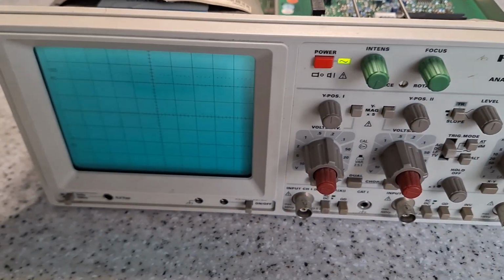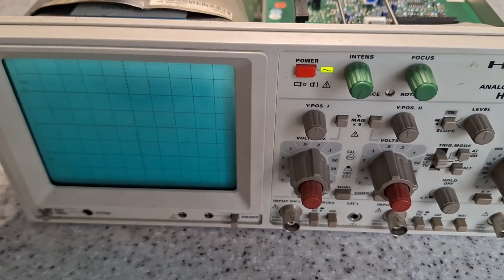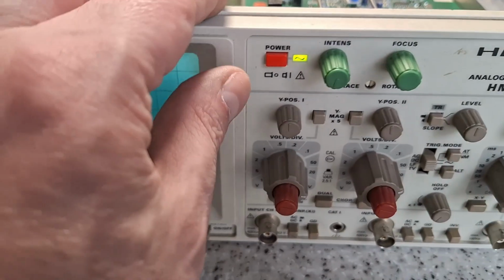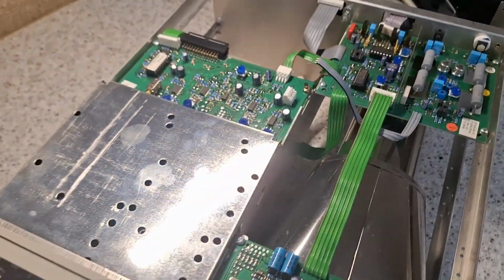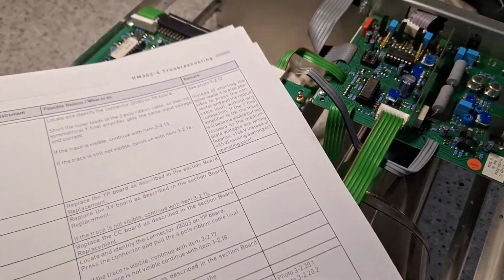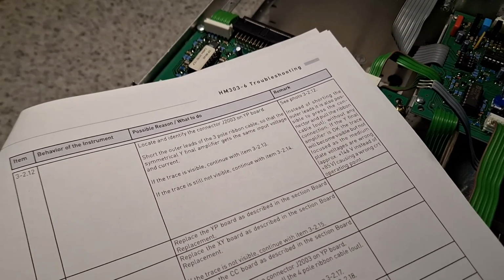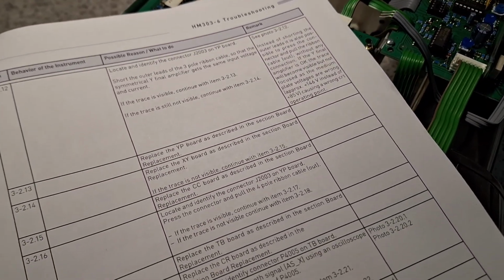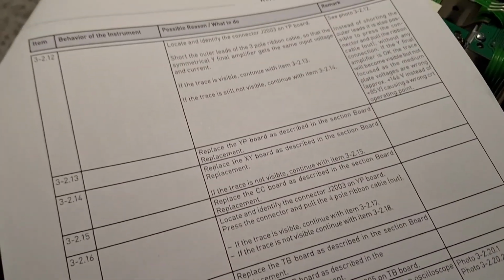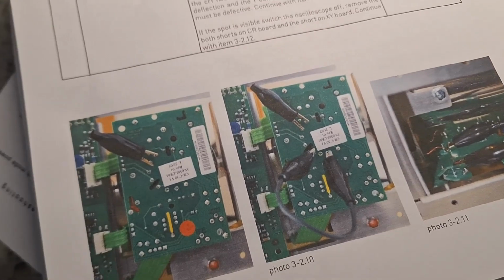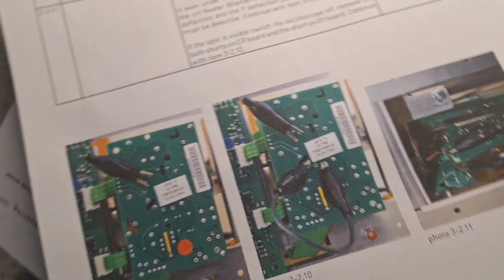Unless it's a fault in the deflection circuit. So what I'm going to do is put an input signal to it and see if there's an input to the deflection board. Okay, so I've had to skip a few things in this troubleshooting manual because this scope appears to have a different CRT to what's shown in the service manual, and it's telling you to short some pins together on the back of the tube. Now mine's different, the pinout's completely different, so I've skipped that step.